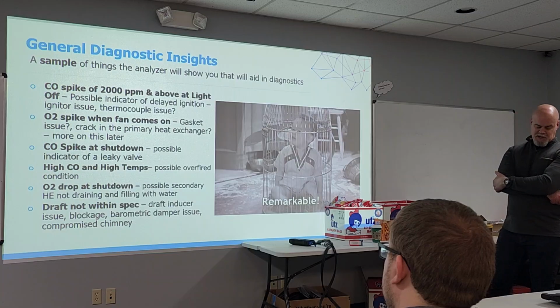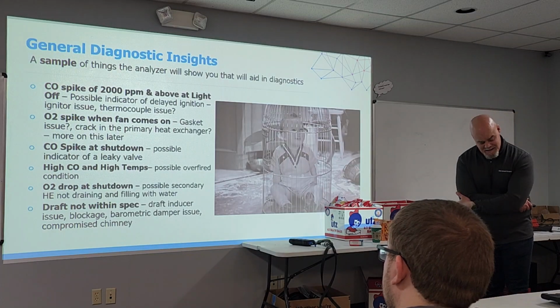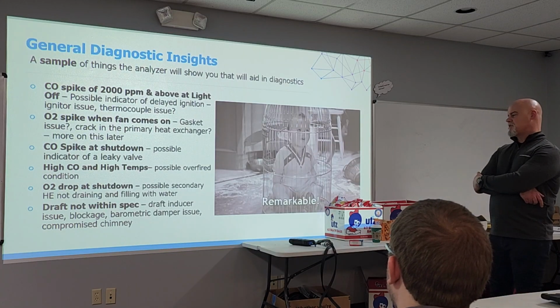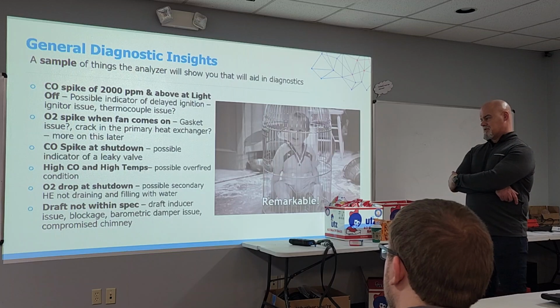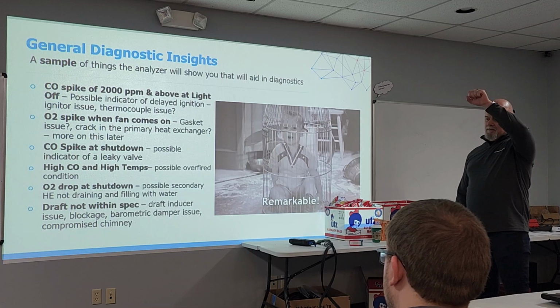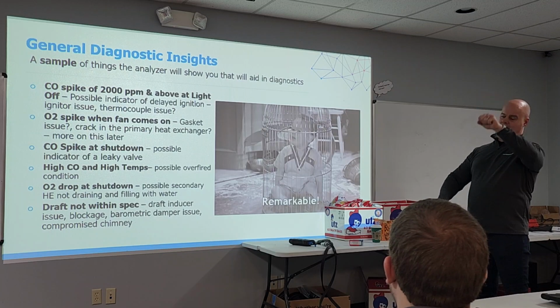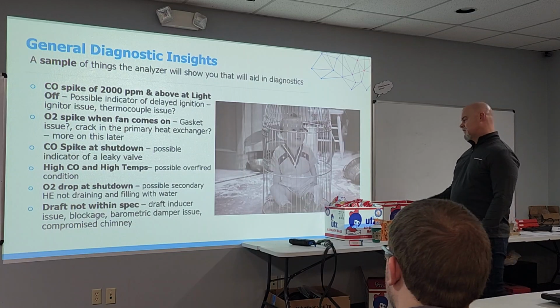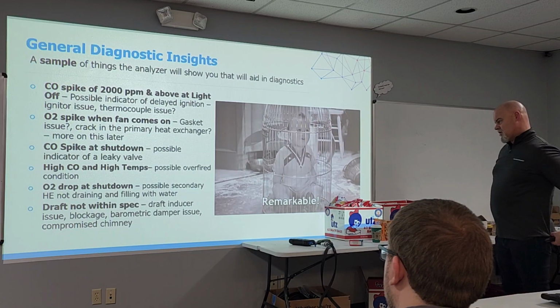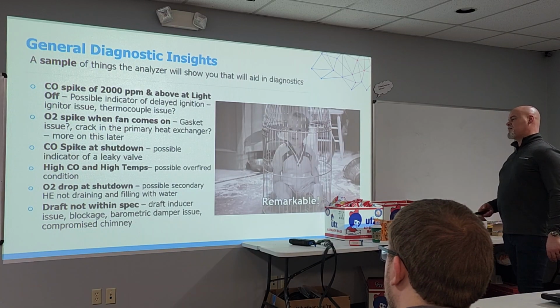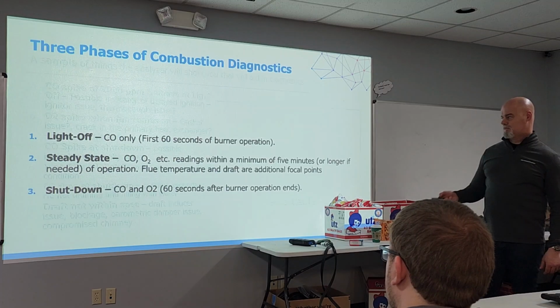Possible secondary heat exchanger not draining and filling with water, and you would see your CO or CO air free go up at that time too, because it's an inverse relationship. When oxygen goes up, CO goes down, but when oxygen plummets, CO is on the rise. Draft not within spec: draft inducer issue, blockage, barometric damper issue, compromised chimney.